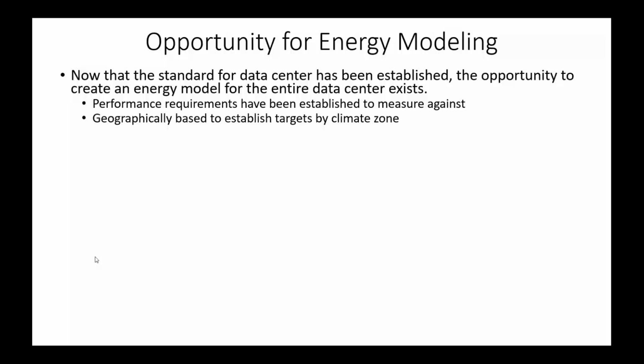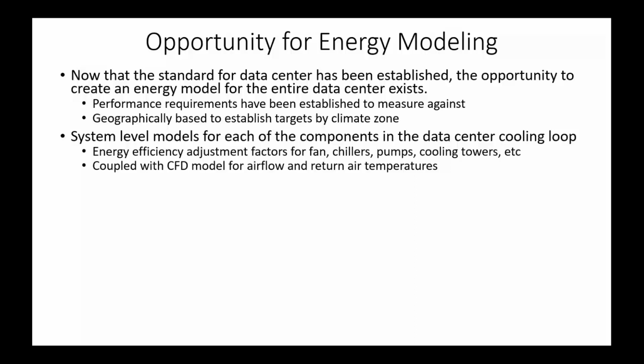You can actually model the cooling system and measure its performance against the criteria that has been set in place by ASHRAE. And it is geographically based on climate zone. And you can develop system level models for each of the components, and that's what we've been working on. So efficiency adjustments for things like fans, chillers, pumps, cooling towers, all of these things have an empirical curve of energy efficiency that is a function of load.